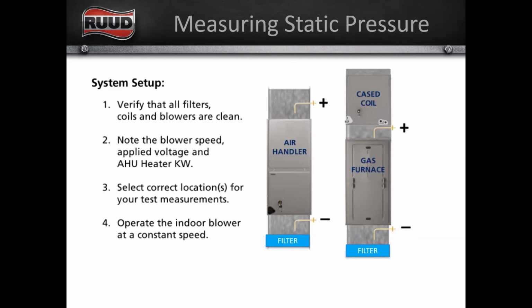So yes, in a perfect world, your return static would be a negative 0.25 and your supply static would be a positive 0.25. If you've got a supply static that is, let's say, 0.1, and you've got a return static that's 0.4, you've got an issue with your return. They should be about equal. Again, in a perfect world, we want to make it as easy to get the air into that blower compartment, or into that blower section, as it is to push the air out of it.